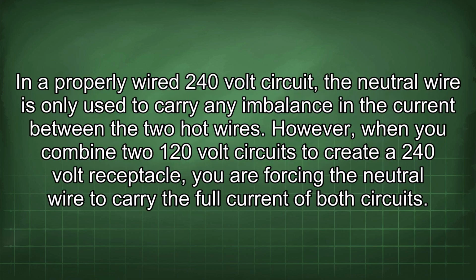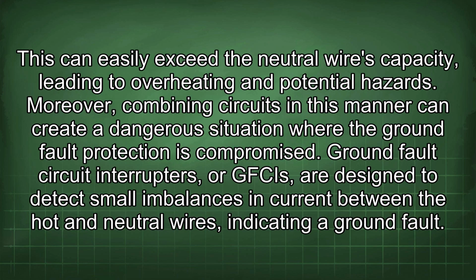In a properly wired 240-volt circuit, the neutral wire is only used to carry any imbalance in the current between the two hot wires. However, when you combine two 120-volt circuits to create a 240-volt receptacle, you are forcing the neutral wire to carry the full current of both circuits. This can easily exceed the neutral wire's capacity, leading to overheating and potential hazards. Moreover, combining circuits in this manner can create a dangerous situation where the ground fault protection is compromised.